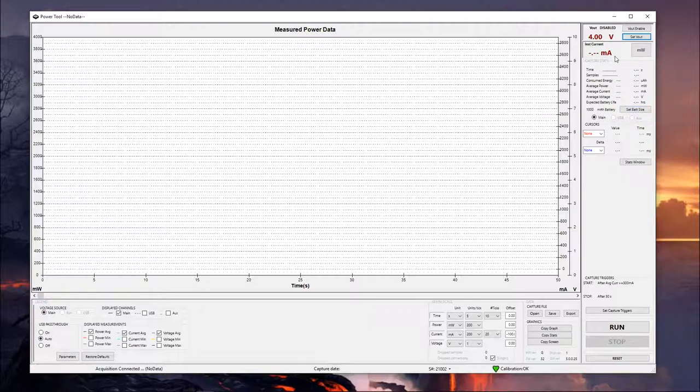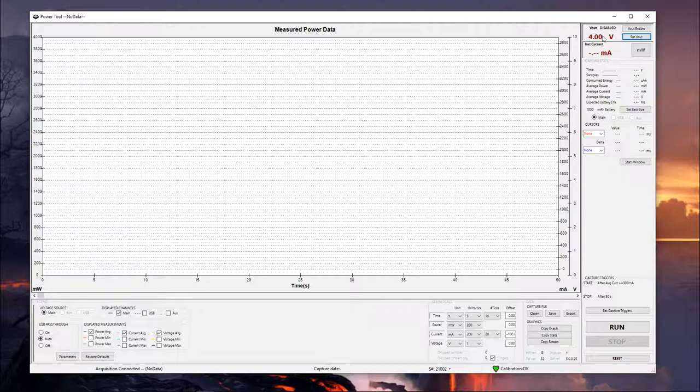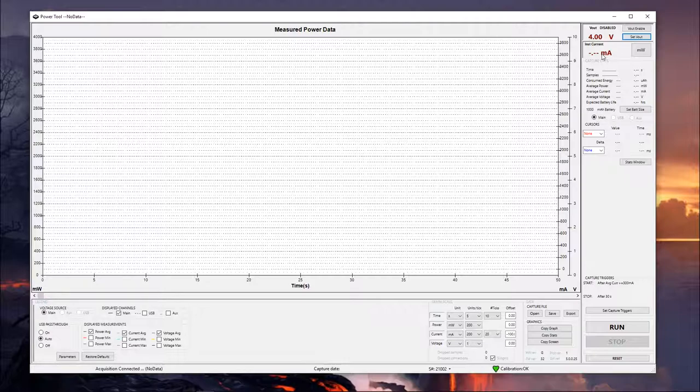Just below that, you see this inst current. It's going to be similar to what the voltage turns into. It's going to turn into a live current measurement. And so that's going to be the momentary instantaneous current, just kind of an average. You can get more specific data than this, but if you're just looking for kind of moment-to-moment general usage details, you can check up in here.